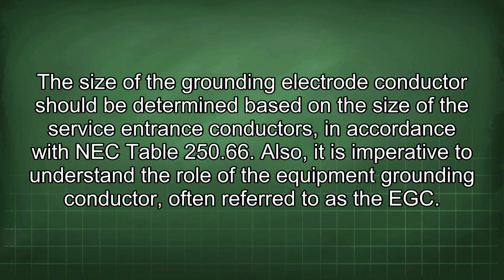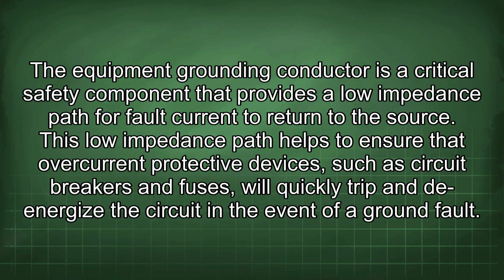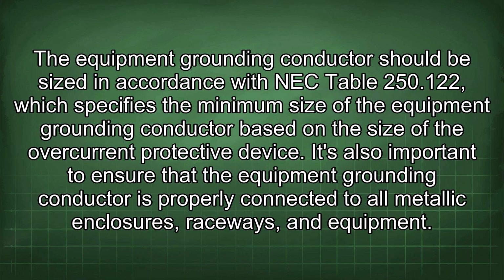Also, it is imperative to understand the role of the equipment grounding conductor, often referred to as the EGC. The equipment grounding conductor is a critical safety component that provides a low impedance path for fault current to return to the source. This low impedance path helps to ensure that overcurrent protective devices, such as circuit breakers and fuses, will quickly trip and de-energize the circuit in the event of a ground fault. The equipment grounding conductor should be sized in accordance with NEC Table 250.122, which specifies the minimum size of the equipment grounding conductor based on the size of the overcurrent protective device. It's also important to ensure that the equipment grounding conductor is properly connected to all metallic enclosures, raceways, and equipment.